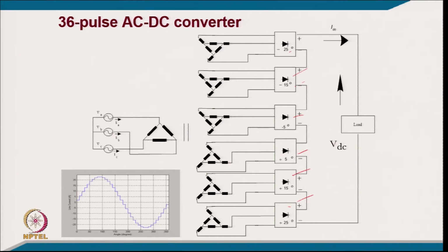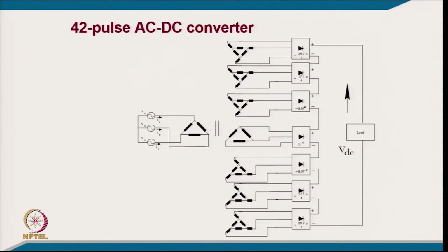In this 36 pulse converter, the lowest harmonic itself will keep reducing, and even the THD will come to less than 3% overall. The transformer leakage reactance further reduces the harmonics in this case. Normally, for the Navy, whether Indian Navy or US Navy, they say that a converter of less than 36 pulse cannot qualify. They require total harmonic distortion in the input supply current of less than 3% with reasonably improved power quality. Of course, because of the diode rectifier, we do not have reactive power burden.